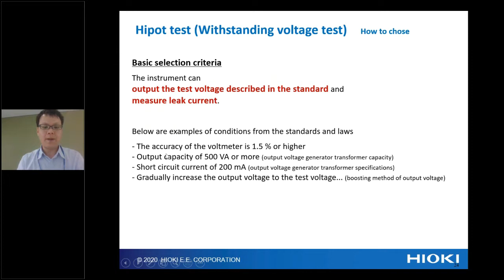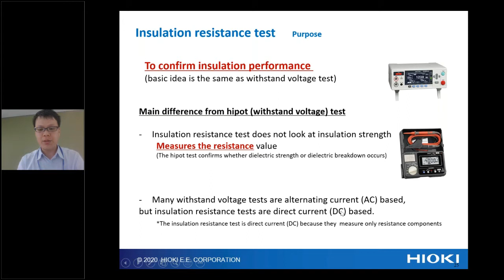Okay, so that's all about the Hipot test. Next, I will move to the insulation resistance test. Firstly, I want to explain about the purpose: to confirm insulation performance. But anyway, the basic idea is the same as withstand voltage testing, with a little difference. So what's the difference between the Hipot test and the insulation resistance measurement? The insulation resistance test does not look at insulation strength. It measures the resistance value. That's why many Hipot tests are alternating current, AC based, but insulation resistance tests are DC based. So it's a different purpose to check.